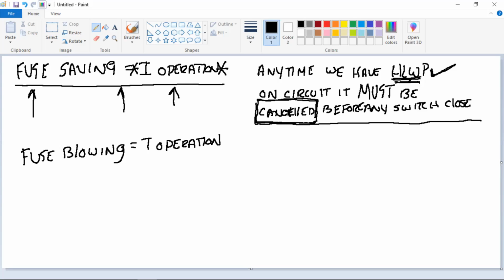Hotline work permit. Yeah. If you close the fuse and for any reason there's a fault on the circuit, a fault on the transformer, a fault on a piece of new equipment or old equipment that you close a fuse on, and you do not give up the hotline work permit, you're going to lock the breaker out because you are in an I operation situation.